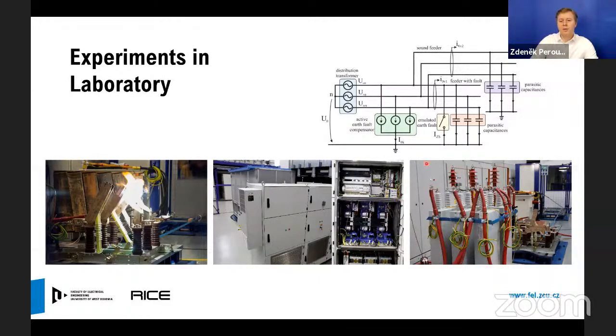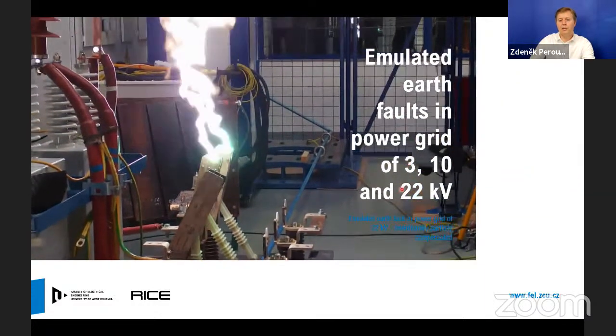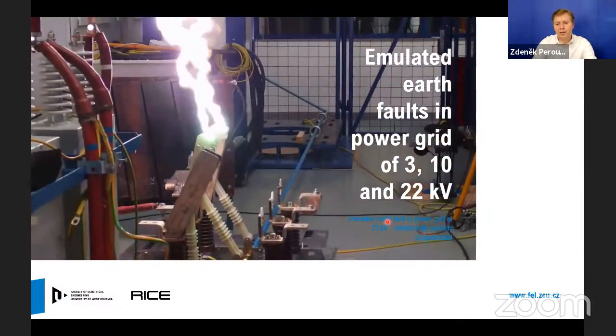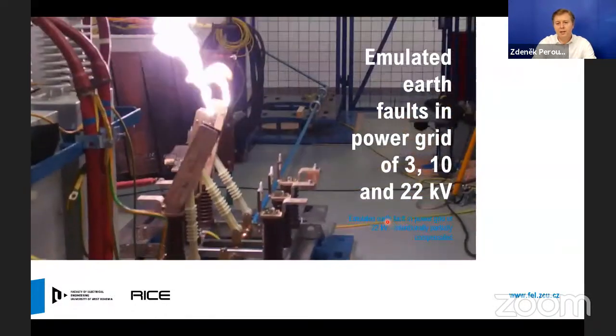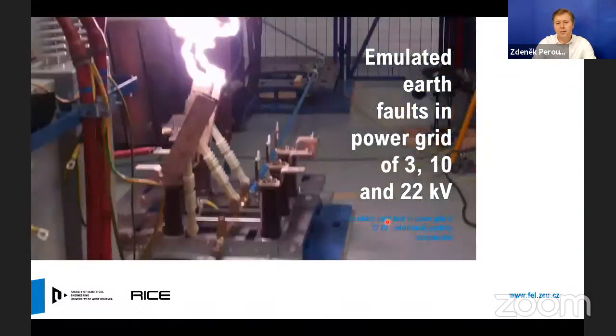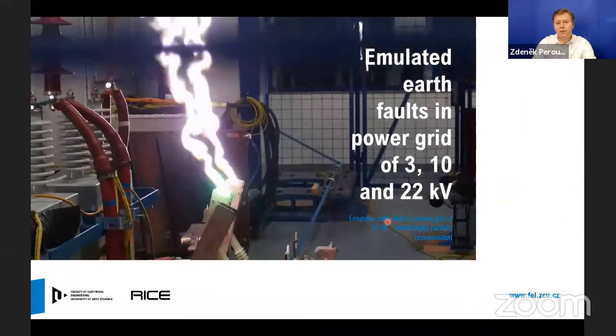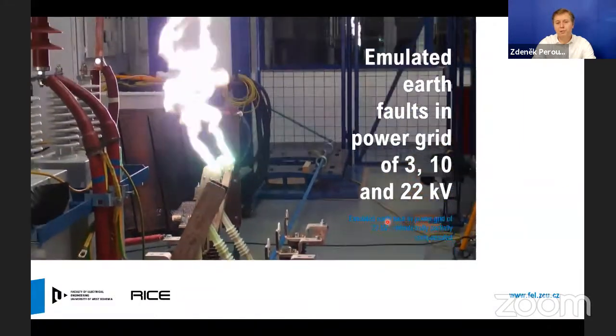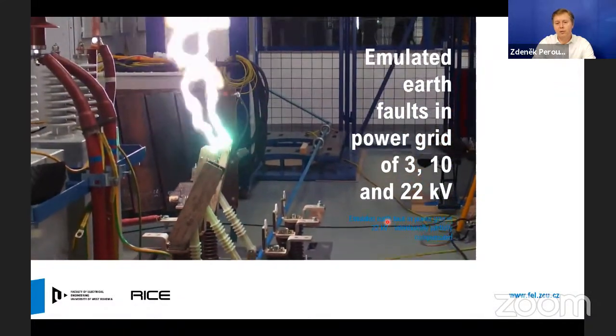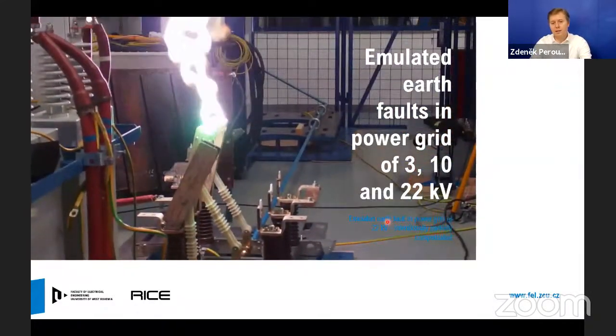The initial test was in a configuration where we built an artificial network with two feeders, the sound feeder and the faulty feeder, where we emulated the ground fault. We did the initial test in the lab at voltage levels of 3, 10, and finally the target 22 kV. Here you can see how dangerous a non-compensated earth fault can be. This video shows what can happen in the system if you do not properly compensate the ground fault current.